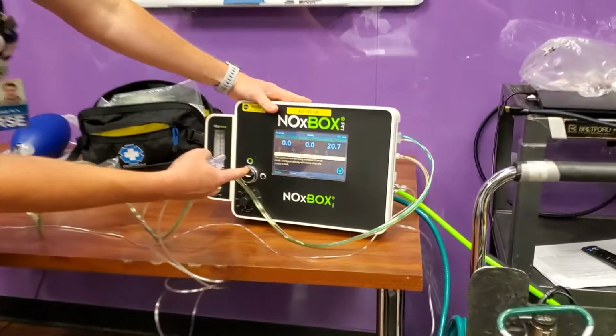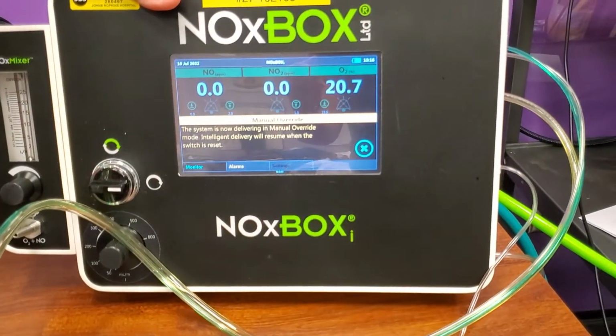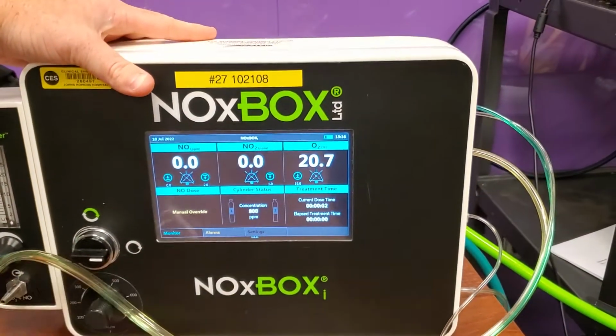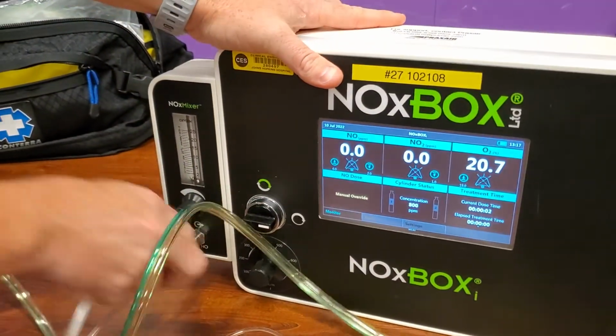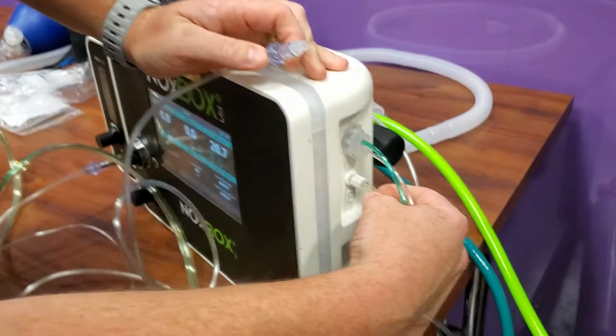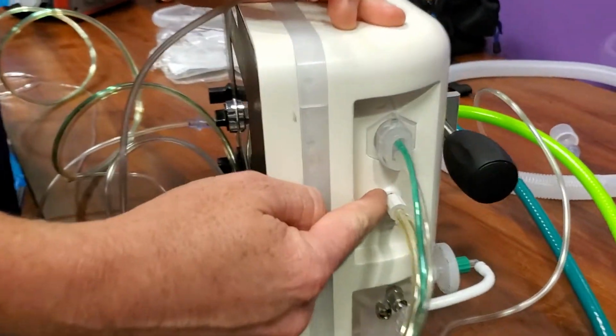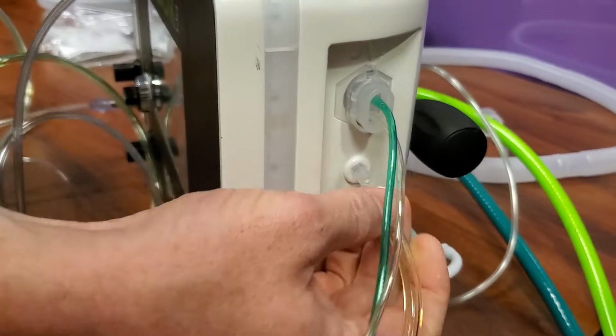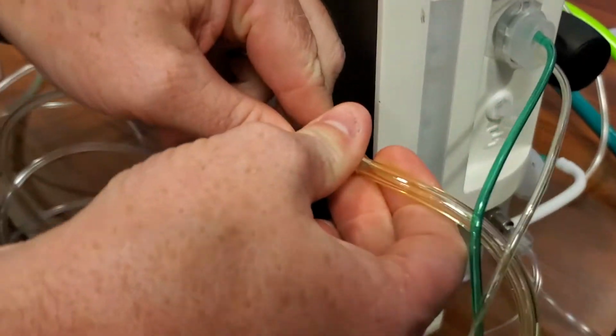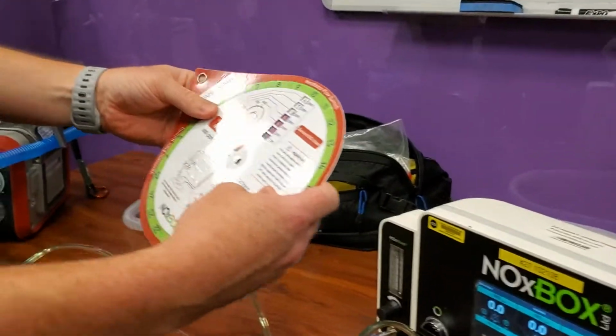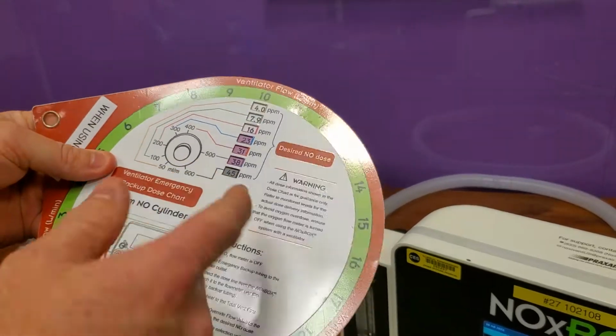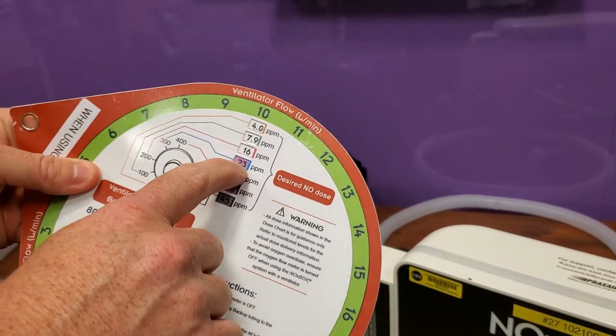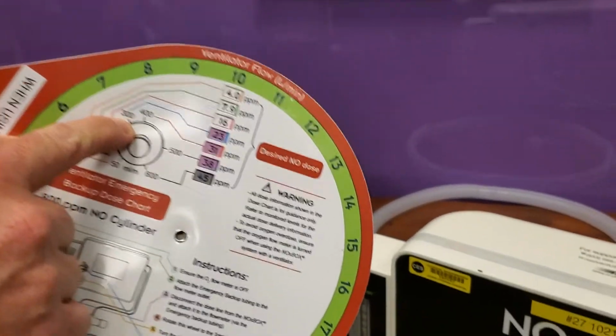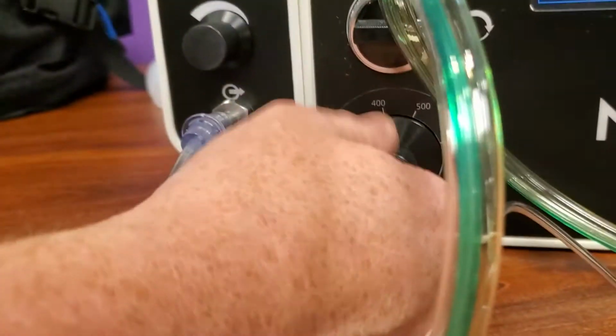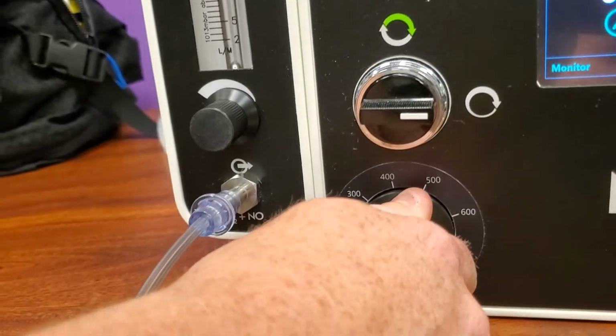It's going to notify us that we're now in our manual override, so it's no longer using the intelligent delivery. We can click the X out of that, and then this is going to go on here, just like a regular flow meter. And this is our nitric delivery line here, the one with the white screw. This piece is going to come out of here and screw onto here, like so. And then this is where we would need our wheel on that red side. So, for instance, if we were looking at a minute ventilation of 10 here, and we were looking for the patient to receive around 20 parts per million, we would be putting our setting right here on about the 300. So we're going to line up with around 300.